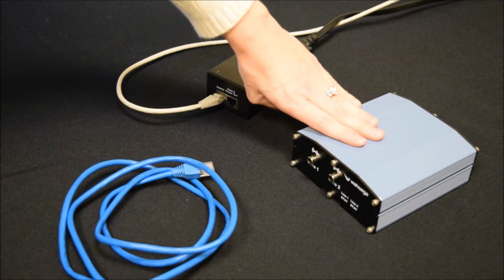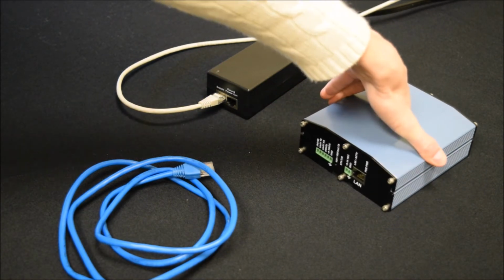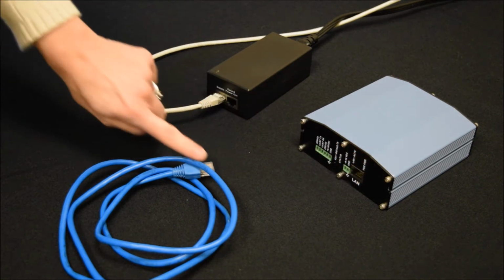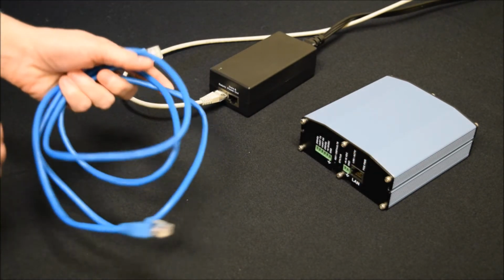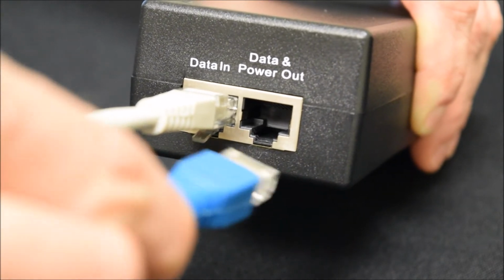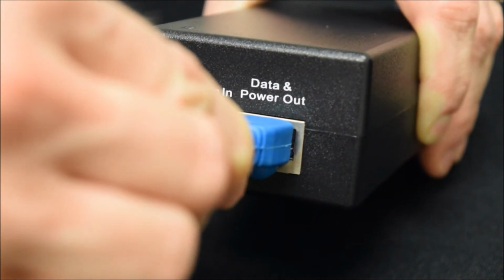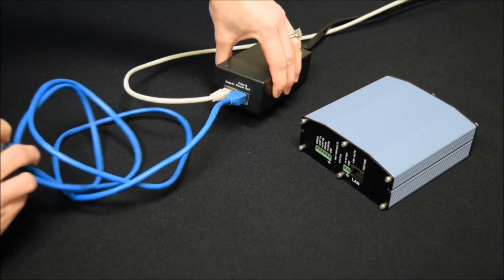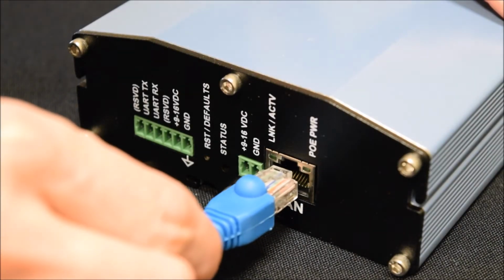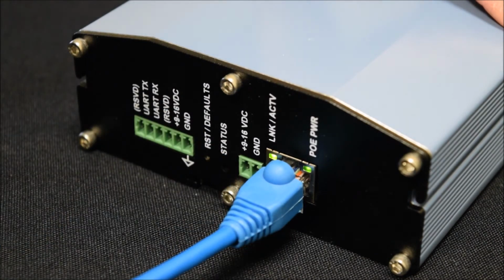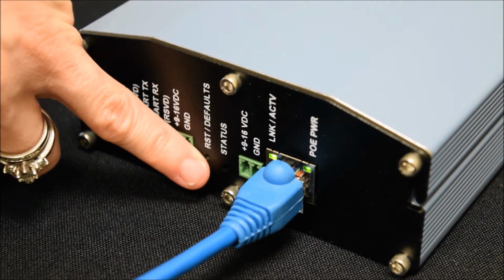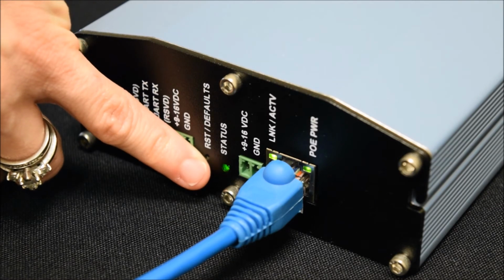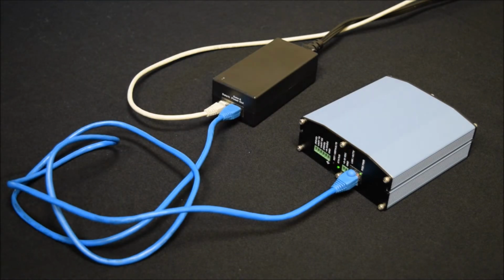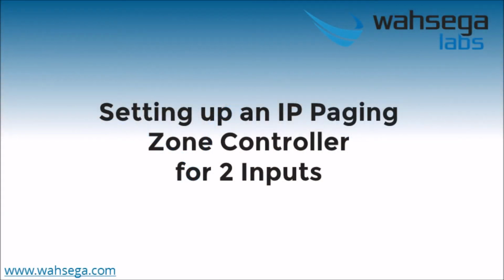Now it's time to supply both to your zone controller. Look for the Ethernet port marked LAN with the PoE power indicator LED. Connect a second Ethernet cable to the port marked data and power out on your PoE injector, and connect that same cable to the zone controller's Ethernet port. You'll immediately see the PoE power indicator light illuminate, and the status LED will begin to stair step. Once the status LED stops blinking and remains solid green, you'll know that your zone controller is online and ready to use.